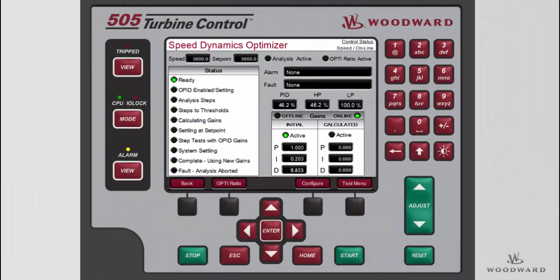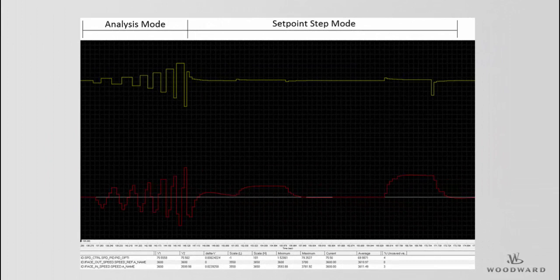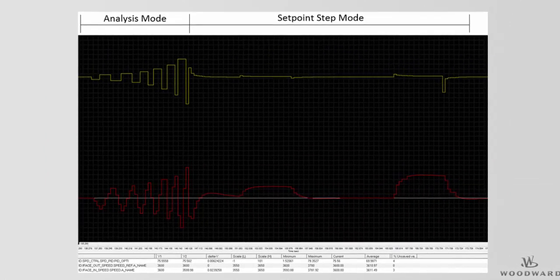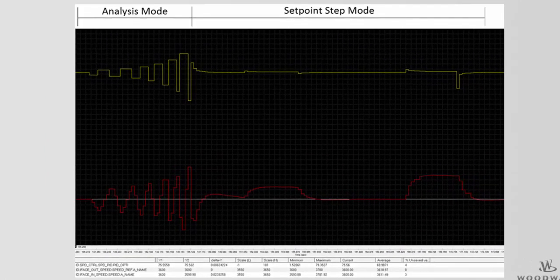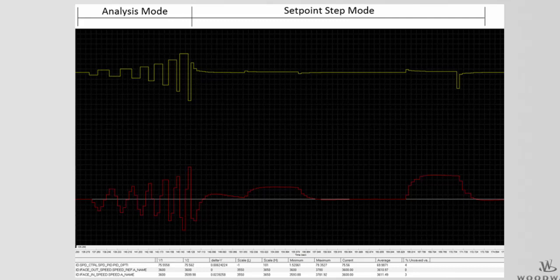We will first overview the optimization test sequence. The Speed PID Optimizer test routine allows the control to automatically analyze the system and calculate the P, I, and D terms for both offline and online dynamic settings. To calculate optimized system dynamics, small and progressively larger adjustments are made to the valve demand in order to measure the turbine system. The optimizer routine remains within user-specified process and valve movement limits to ensure that the turbine system remains within acceptable operating limits.